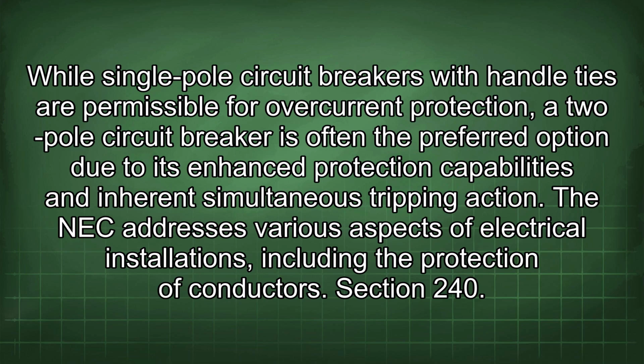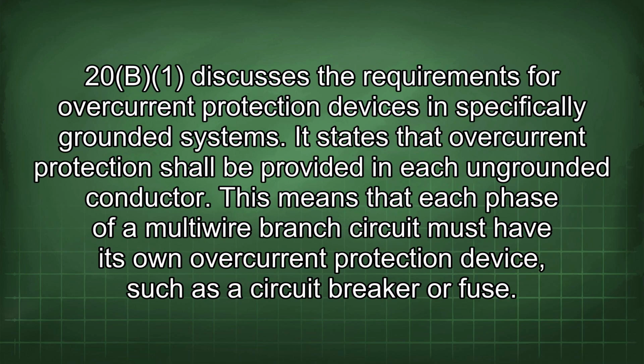The NEC addresses various aspects of electrical installations, including the protection of conductors. Section 240.20(B)(1) discusses the requirements for overcurrent protection devices in solidly grounded systems. It states that overcurrent protection shall be provided in each ungrounded conductor. This means that each phase of a multi-wire branch circuit must have its own overcurrent protection device, such as a circuit breaker or fuse.